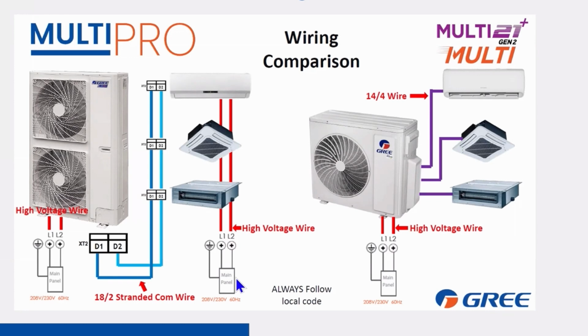MultiPRO is done differently. You will have a power source, and it could be an individual power source or shared power to each of the indoor units, but that has nothing to do with your communication. That is going to be your 18-2 stranded comm wire, run as a daisy chain from the outdoor unit to your indoor units, and then daisy chain from there to the next one, and the next one. Your power supply for outdoor and your power supply for indoors are completely separate, unless you use that adapter we showed you in the quick reference guide, where you could actually power the indoors from the outdoor unit. Again, if it's a new installation, I would highly recommend that you come out of the breaker panel and have a separate circuit, not power it off the outdoor unit.